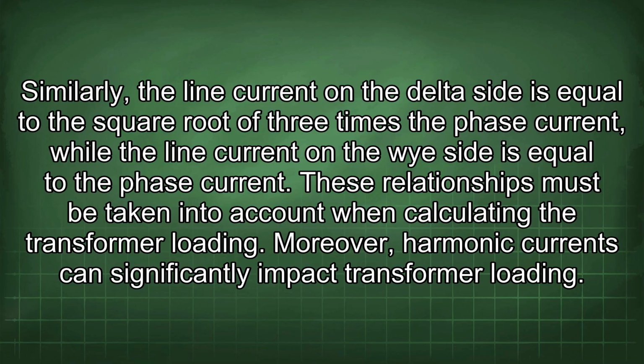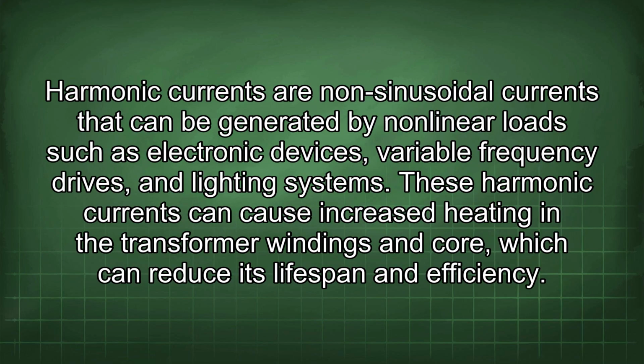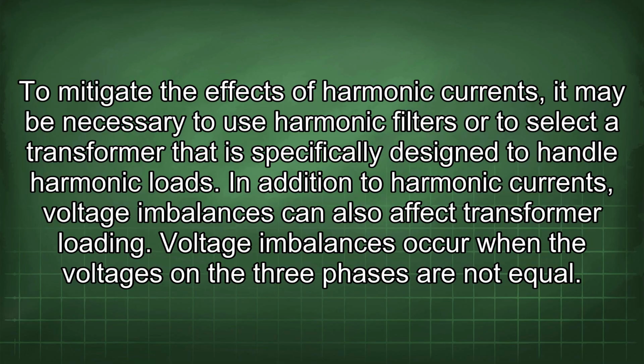Moreover, harmonic currents can significantly impact transformer loading. Harmonic currents are non-sinusoidal currents that can be generated by nonlinear loads such as electronic devices, variable frequency drives, and lighting systems. These harmonic currents can cause increased heating in the transformer windings and core, which can reduce its lifespan and efficiency. To mitigate the effects of harmonic currents, it may be necessary to use harmonic filters or to select a transformer that is specifically designed to handle harmonic loads.